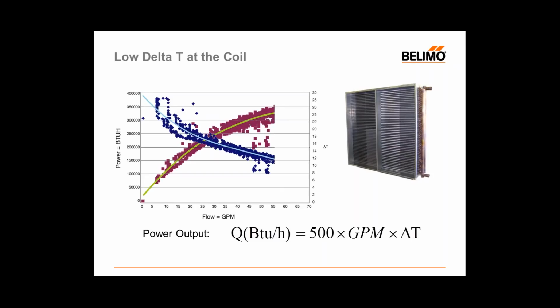So what low delta T really means at a coil is that you didn't expend the energy in that water efficiently. So we spend a lot of money to make our water very cold. We put it through our coil, and maybe it's supposed to come out 12, 14, even 16 degrees warmer than we put it in, but it only comes out 8, 10, or 12 degrees warmer. Well, then we didn't use all of the energy that was available to us in that water, and so that's why we talk about inefficient heat transfer at the space.